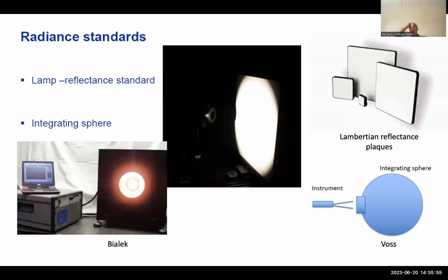The big thing with the radiance standards, these reflectance plaques we just talked about, is that they're as close as possible to Lambertian reflectance plaques, meaning the light is getting reflected equally in all directions off of this plaque. So there are no patterns that you can see in the reflectance across this plaque.